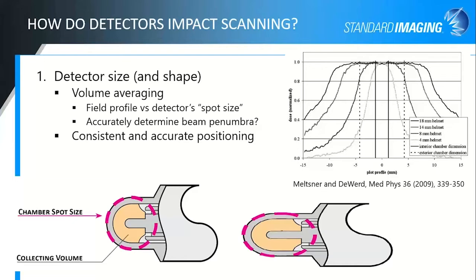We would like to determine the beam penumbra accurately as you're doing your scanning, and the integration of that fall off, as well as any peak, like in this gamma knife plot that I have from a publication from Meltsner and DeWerd. Your detector will average over that, and I'm sure all of you know that, but it's a good thing to be aware of.